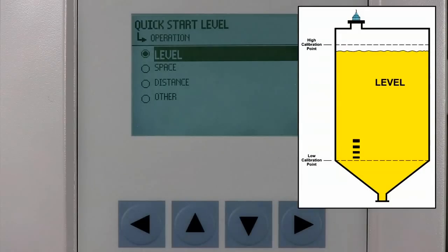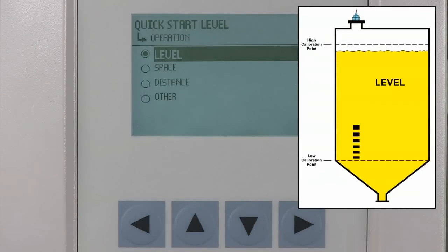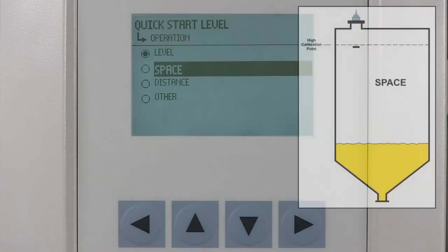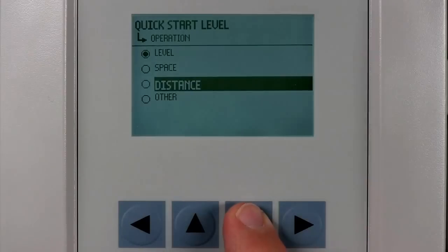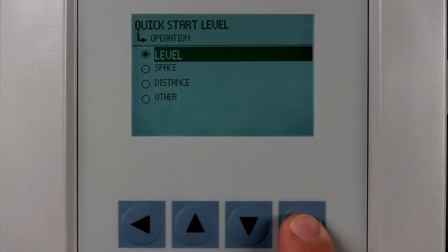The level mode measures the height of the material in the vessel from the low calibration point to the high calibration point. The space mode measures the distance from the high calibration point to the material surface. The distance mode measures the distance from the transducer face to the material surface. In our application, we will select the level mode.